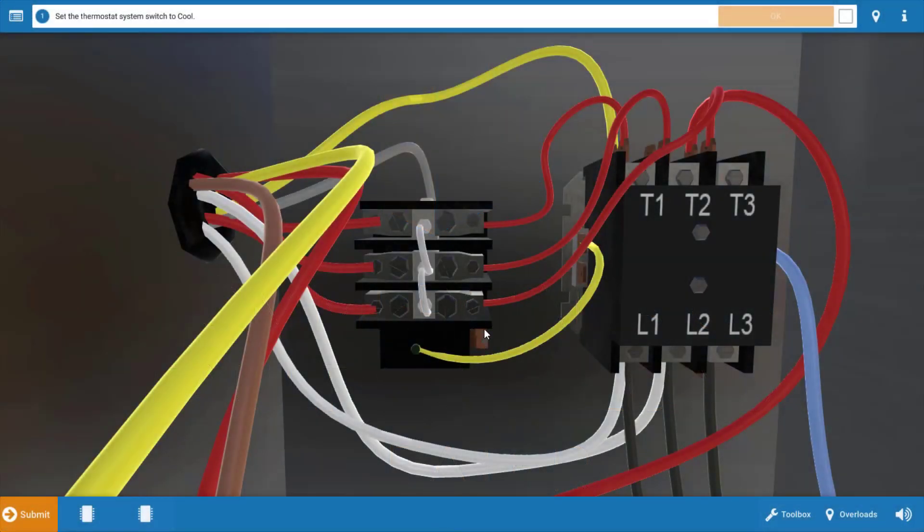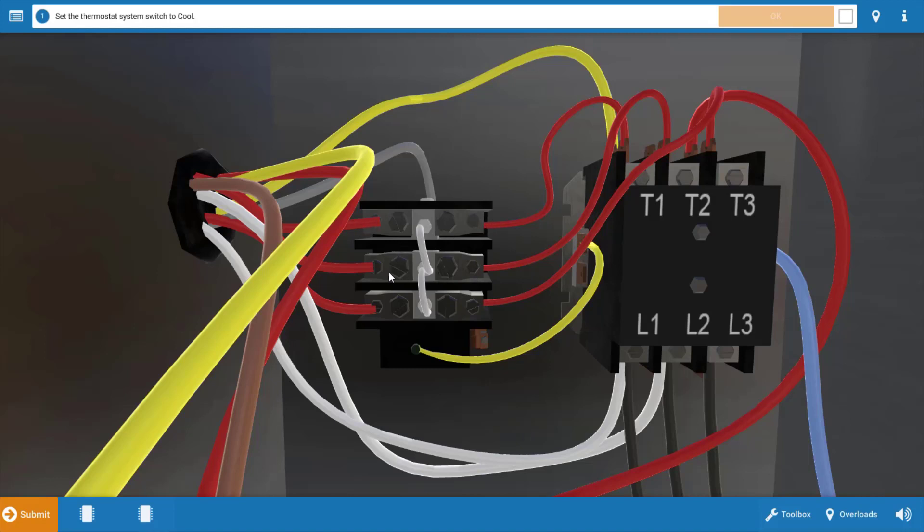Just a brief description of what we call these pilot duty overloads. There's one on each hot leg of the compressor and they're comprised of two parts. They have a heater that's in series to each winding of the compressor across these red connections, and in close proximity to those are three normally closed switches that are not connected to the heaters but are in close proximity. So if the compressor draws high current, the heater will heat up and trip its corresponding bimetal switch.